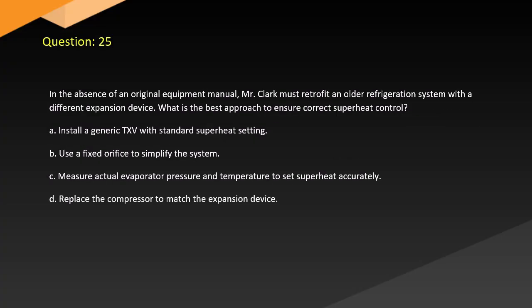Question 25. In the absence of an original equipment manual, Mr. Clark must retrofit an older refrigeration system with a different expansion device. What is the best approach to ensure correct superheat control? A. Install a generic TXV with standard superheat setting. B. Use a fixed orifice to simplify the system. C. Measure actual evaporator pressure and temperature to set superheat accurately. D. Replace the compressor to match the expansion device.